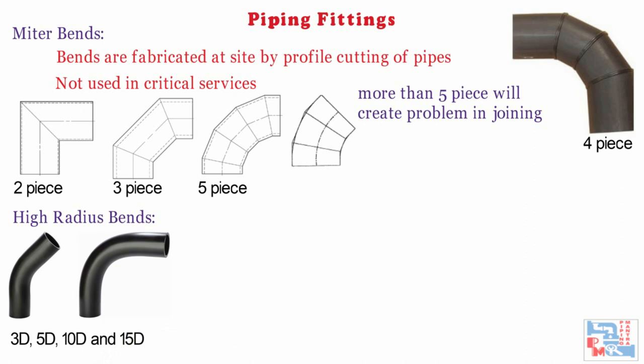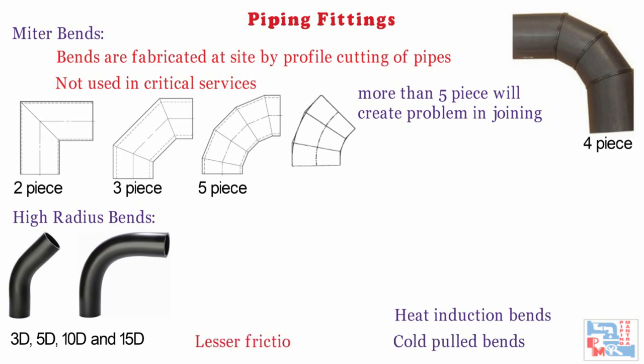These large-radius bends are usually used in viscous and slurry services like paint and chemical chips flowing through pipes. This fitting is also called a heat induction bend or cold-pulled bend. These have less friction losses compared to standard 90-degree elbows.